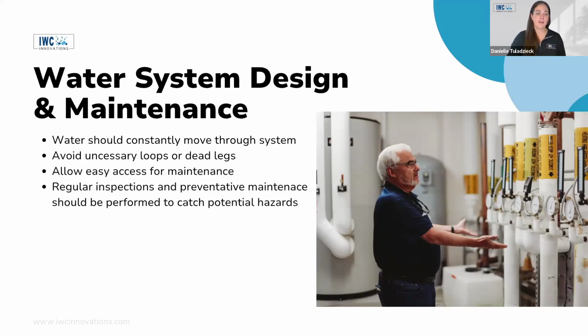Water system design. Good design is a foundation of prevention. Systems should be designed to keep water moving, avoid unnecessary loops or dead ends, and allow easy access for maintenance. Plumbing material selection matters, size matters. Oversized pipes and systems can lead to stagnation, while undersized systems can have pressure issues.